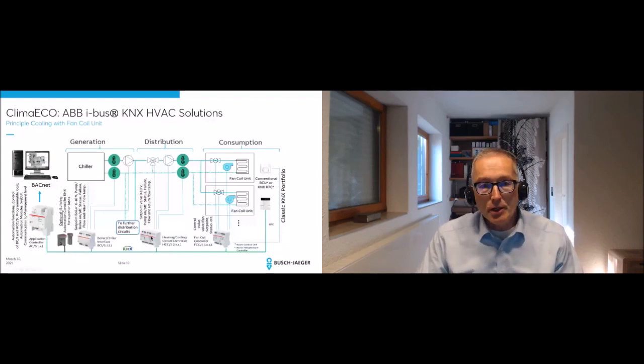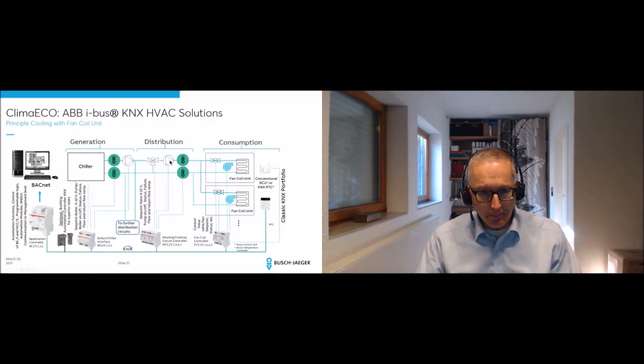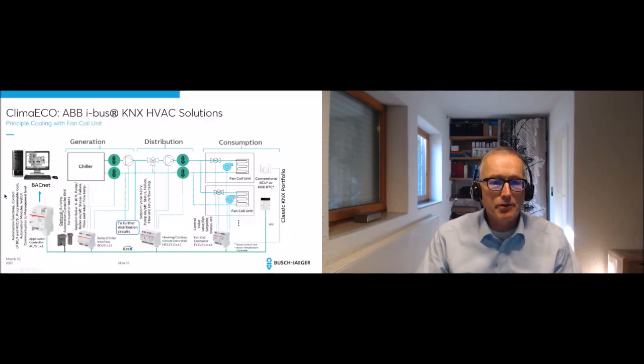Furthermore, for the generation of hot and cold water in our building, we can also interface with the boiler chiller interface. And then, of course, supply also here the right amount of water and the right temperature for the whole solution behind. And the whole building can consist of many, many heating or cooling circuits. And on top, we have to manage everything. We have to visualize everything. We have to send values maybe via BACnet to another system, a superior building management system. All these things can be done by the application controller.